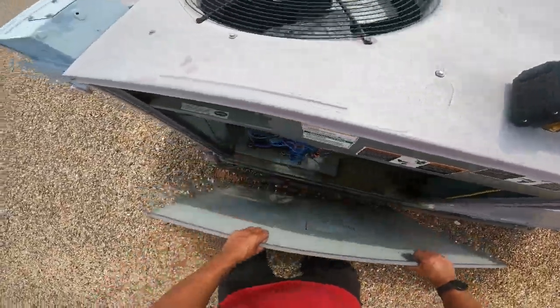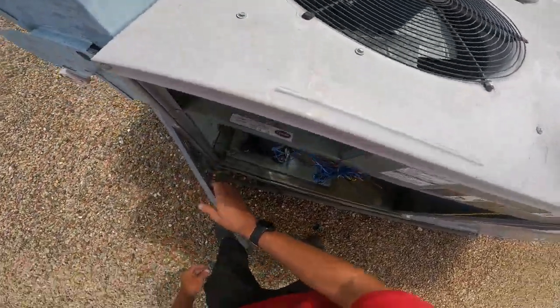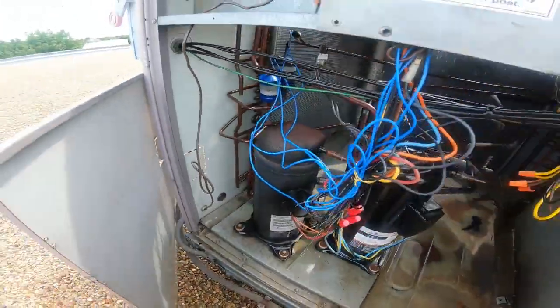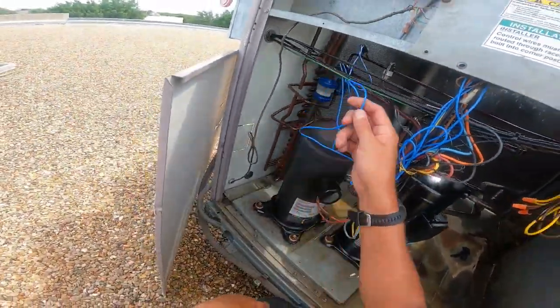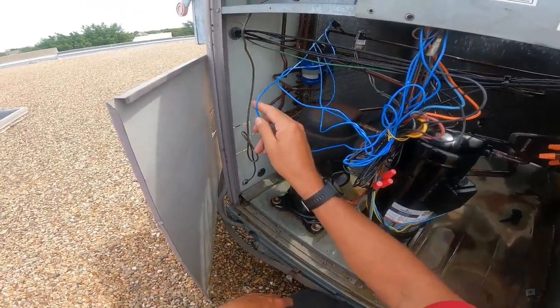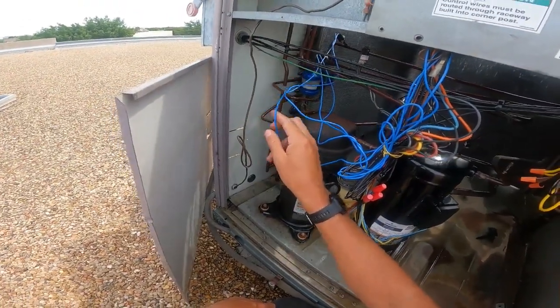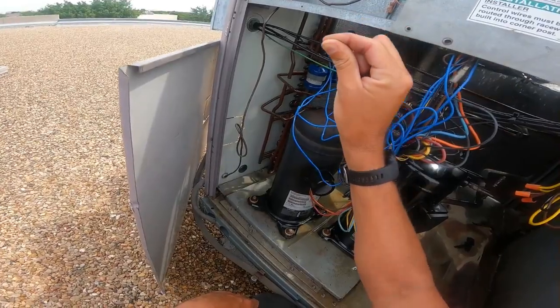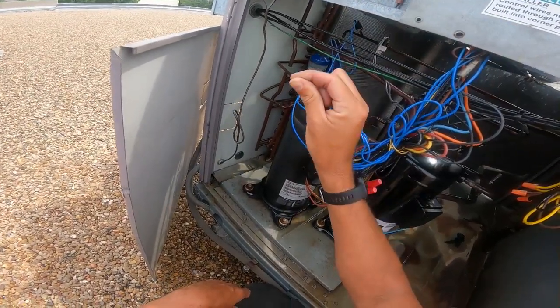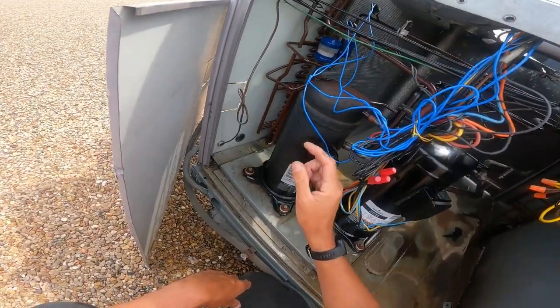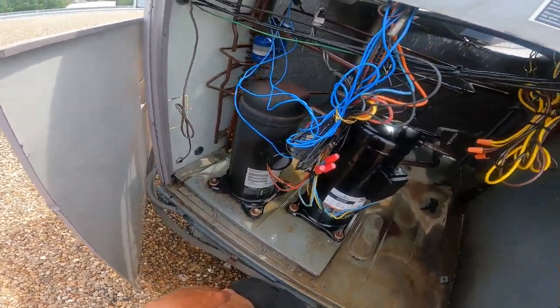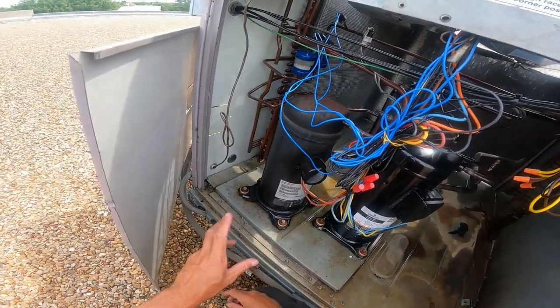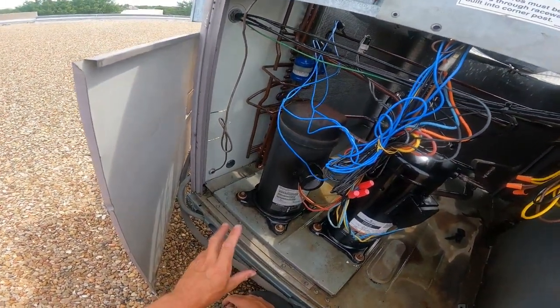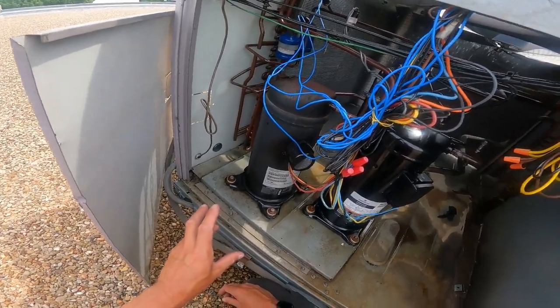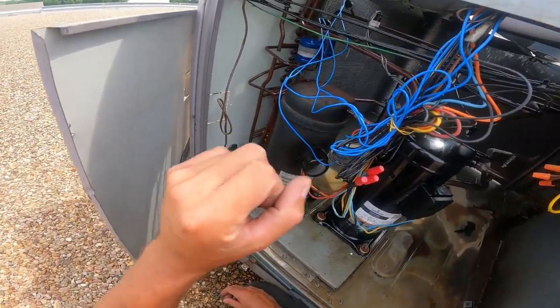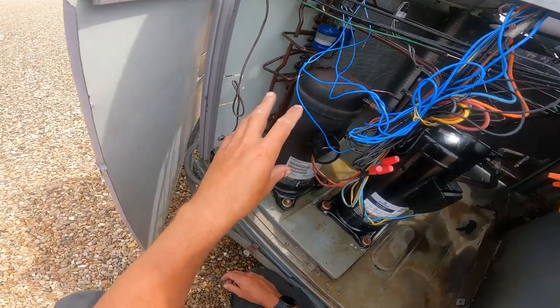So we need to get this other compressor running, and then the one that's obviously cracked open. Oh look, guys, the freaking pressure switches are bypassed. God, that just makes me so mad. Because of that, somebody could have completely ruined this compressor, just because you wanted to bypass a pressure switch. They're there for a reason, people, to keep things like this from destroying a compressor. Luckily, this compressor's still running.